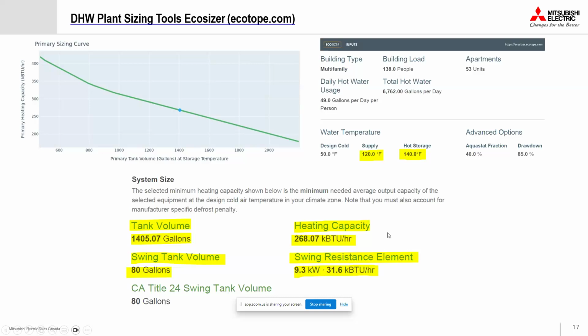Here, like 260,000 BTUs per hour, that's the size of the equipment you require. But remember that if you are sizing a heat pump, size your heat pump at the lowest design temperature of your area. Let's say I'm at like minus 18 or minus 20 degrees Celsius, your heat pump should deliver this capacity. And the last thing here is the resistance heater for the swing tank. That is also provided, at 9.3 kilowatts, along with the tank size.